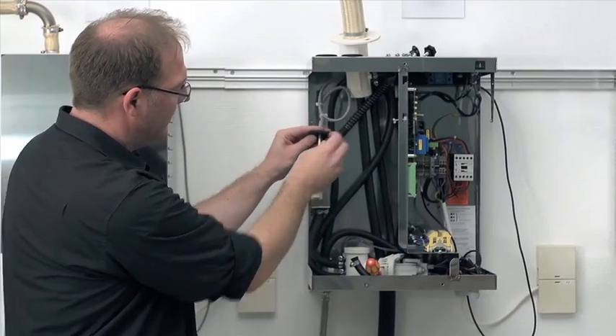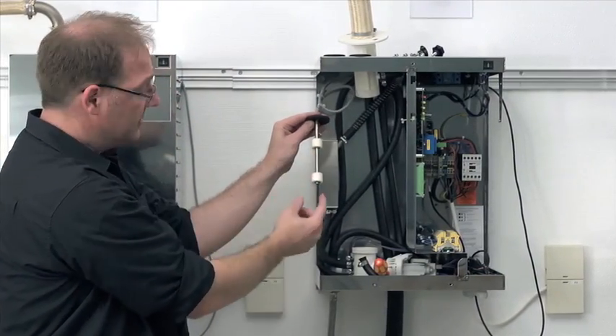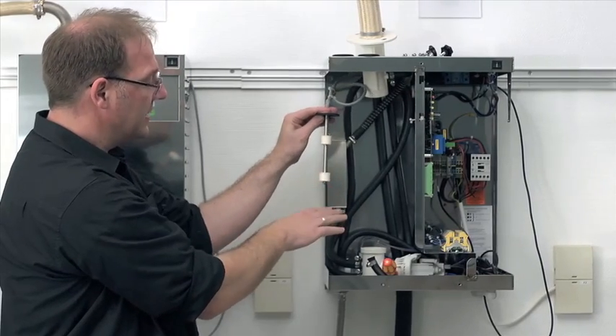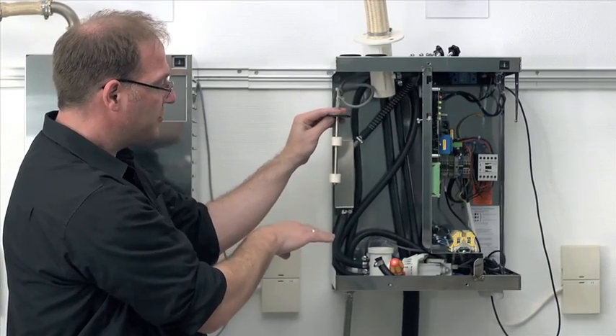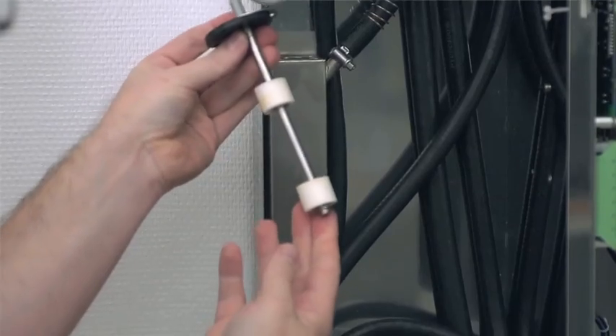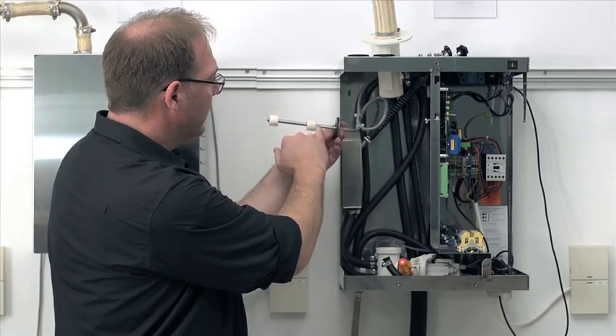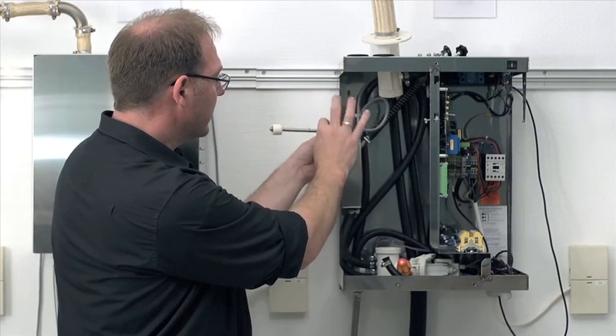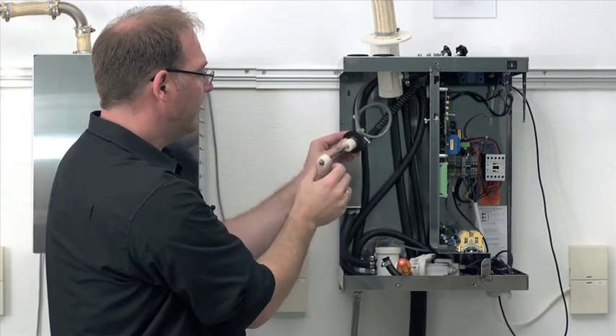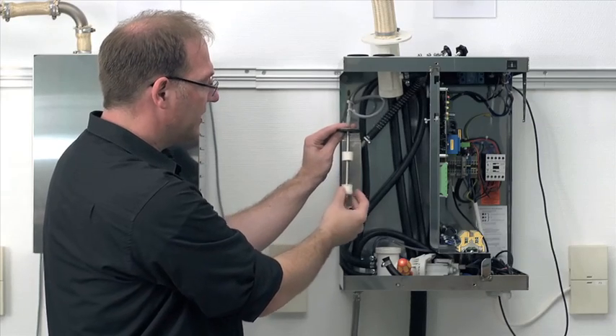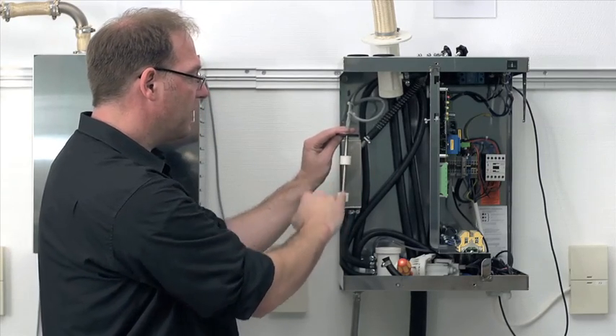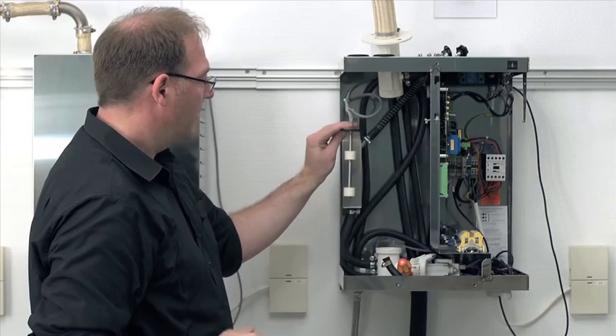And then I can just pull the floating switch up and out. The floating switch itself is made up of the following: the rod assembly has two floaters on it, which rise up when the water level is correspondingly high. Now I can go about this with some cloth, for example, cleaner, and see to it that I remove all mineral deposits carefully. Because these floating switches, or rather these two floaters here, do have to be able to float up and down very freely.